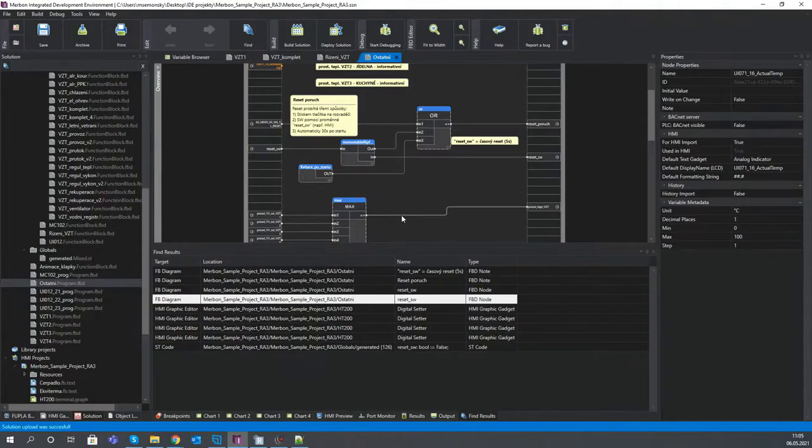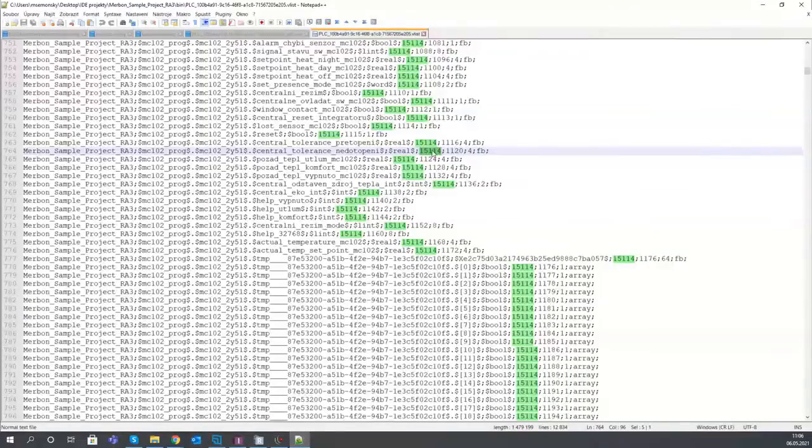If we have some variable which is in the middle of the memory and we change the variable type, like from integer to real, which means that it has 4 bytes rather than 2 bytes, because the integer has 2 bytes, and if we change it to real, it has 4 bytes. So we need to place for another 2 bytes. This means that we have to rearrange the memory somehow, and take this variable and put it to the end of the list, for example, to get a continuous 4-byte space, which may result in changes in these COM IDs.